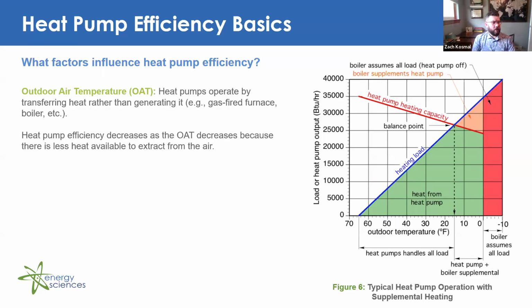Okay. So if we turn our attention to the figure at the right, this is a typical heat pump operation with supplemental heating. And so you can see that the heating load, as shown by the green triangle, is met by only the heat pump until that outside air temperature drops below 15 degrees Fahrenheit. Okay. And at that point, the heating load requires supplemental heating from the boiler. So an example of supplemental heating from a boiler, if you have large office windows in your facility, you may have a perimeter heating loop. This could be one example of supplemental heating. Another could be heating hot water coils within your duct system that only fire on during these supplemental heating periods.